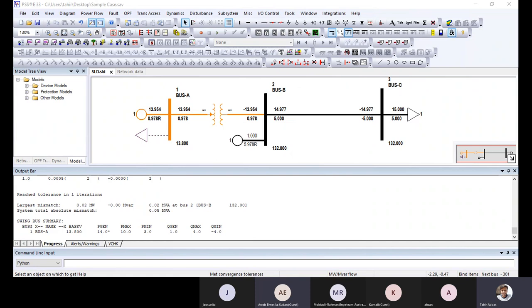This is related to the reactive capability curve, because as a system operator you should know about the reactive capability. Once you go into a negative region, there will be a heating effect, and if you go into a high positive region, then there will be a loss of synchronism. The generator cannot absorb like this.